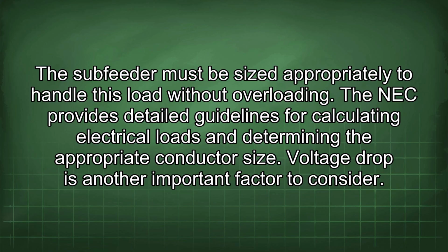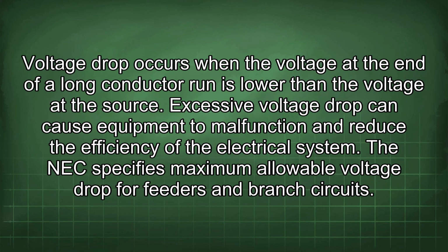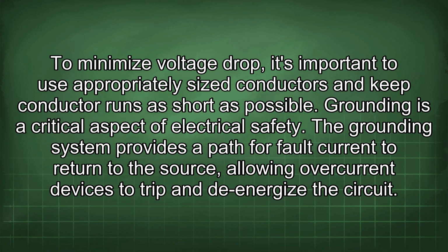Voltage drop is another important factor to consider. Voltage drop occurs when the voltage at the end of a long conductor run is lower than the voltage at the source. Excessive voltage drop can cause equipment to malfunction and reduce the efficiency of the electrical system. The NEC specifies maximum allowable voltage drop for feeders and branch circuits. To minimize voltage drop, it's important to use appropriately sized conductors and keep conductor runs as short as possible.